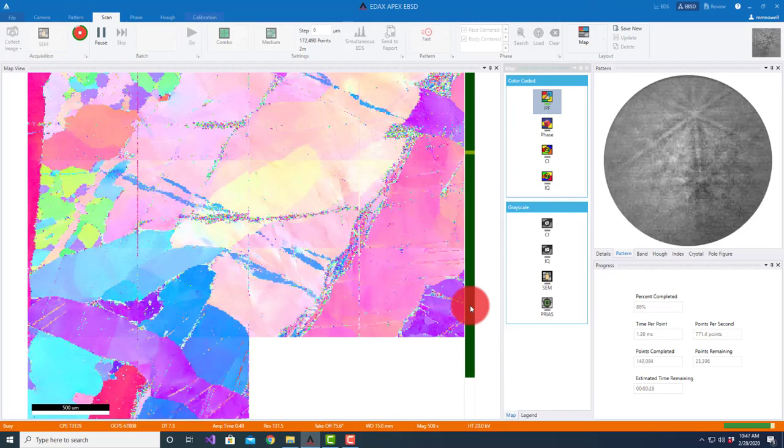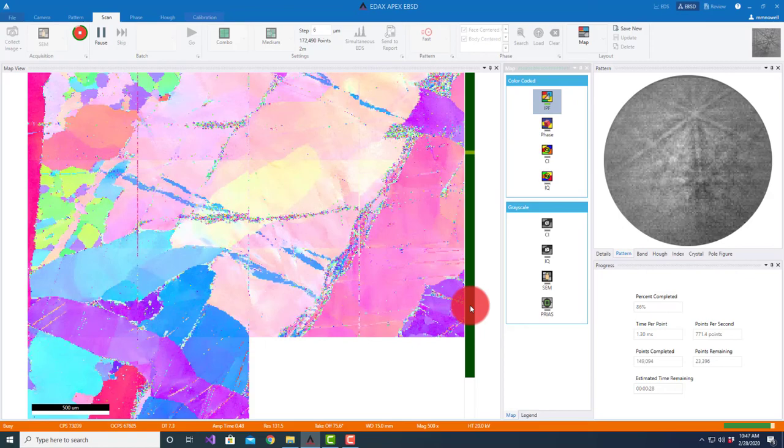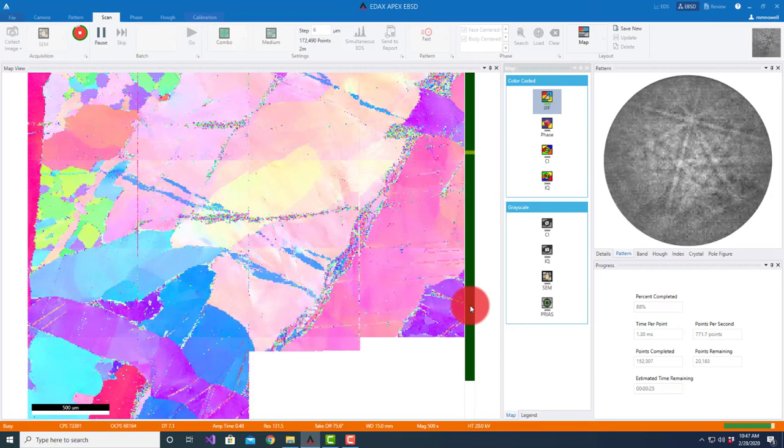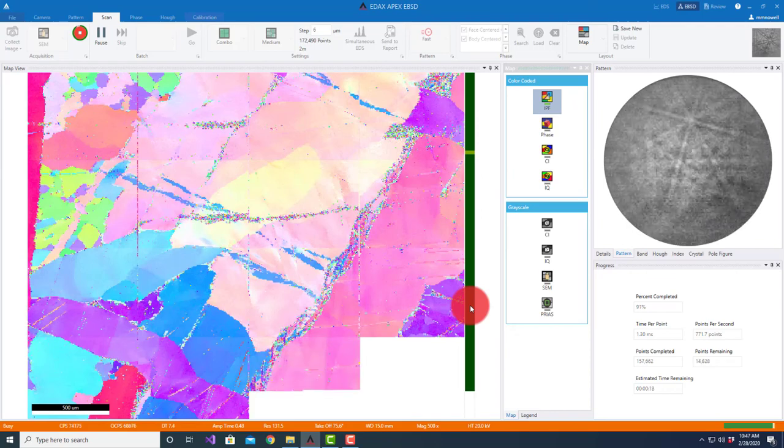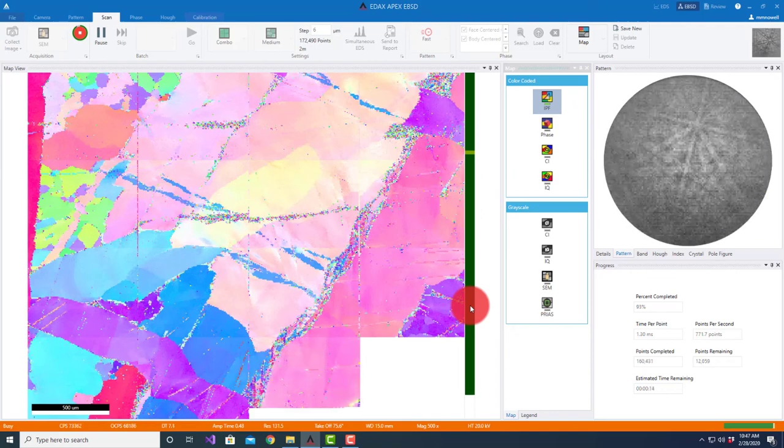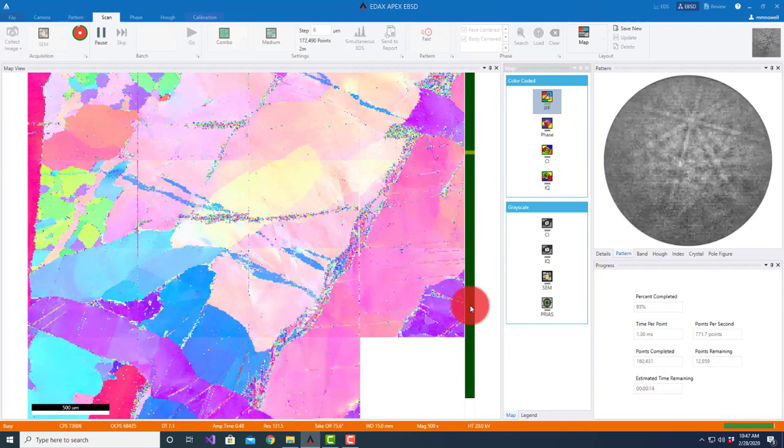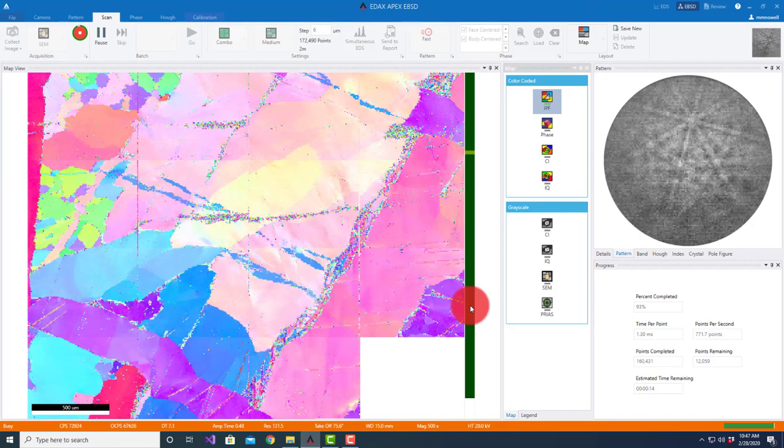You need to make sure you've measured your sample angle because you can go and focus at different points on the sample to make sure, using your x, y, and z position, are you really at 70 degrees like we're assuming or are we off? Being off a half a degree will of course cause some projection distortions in the data.